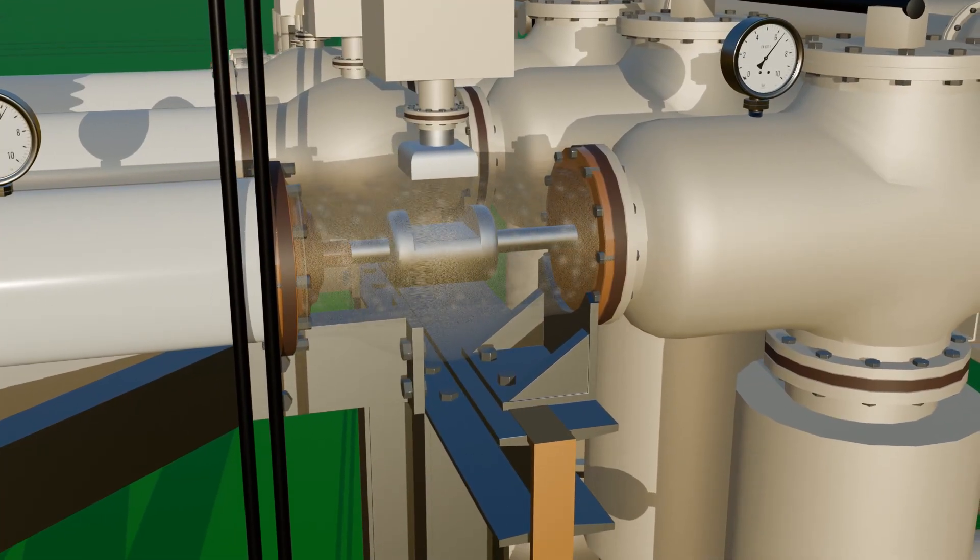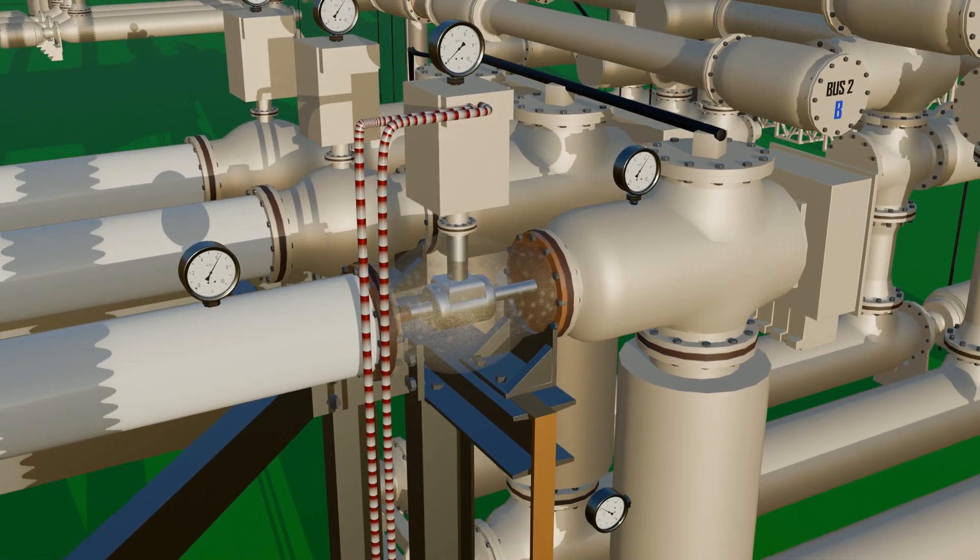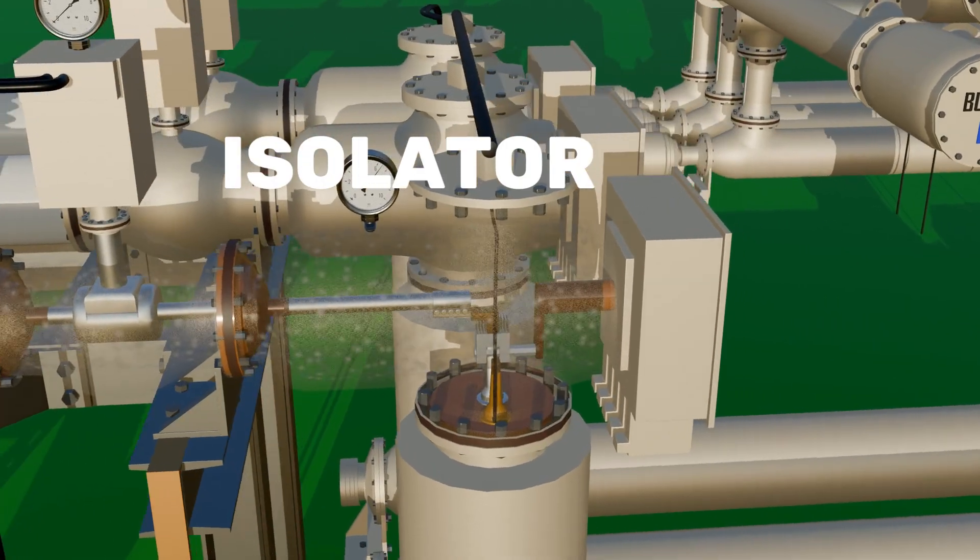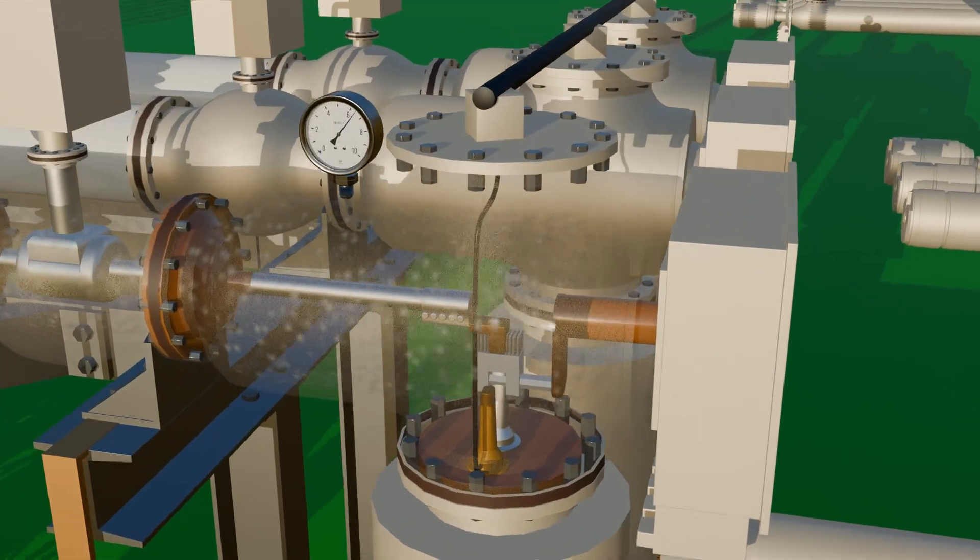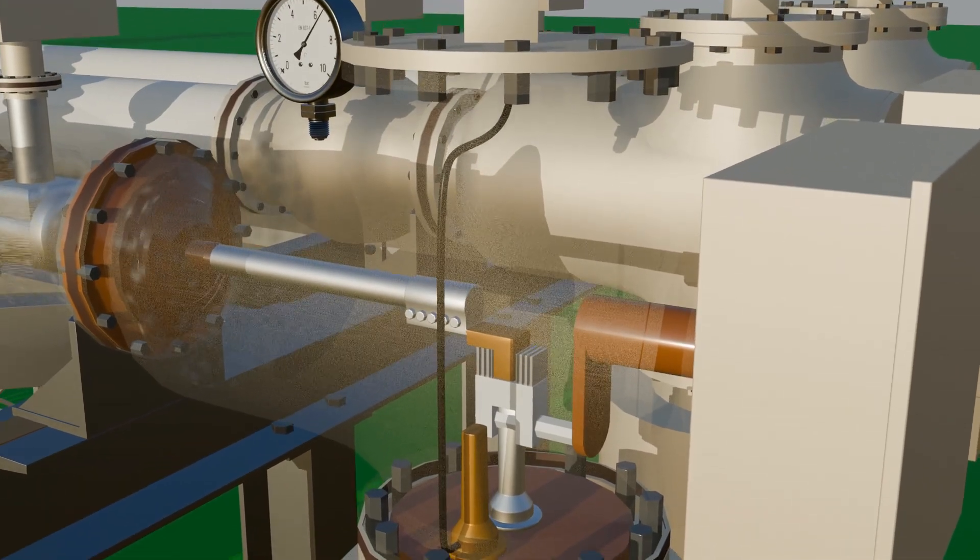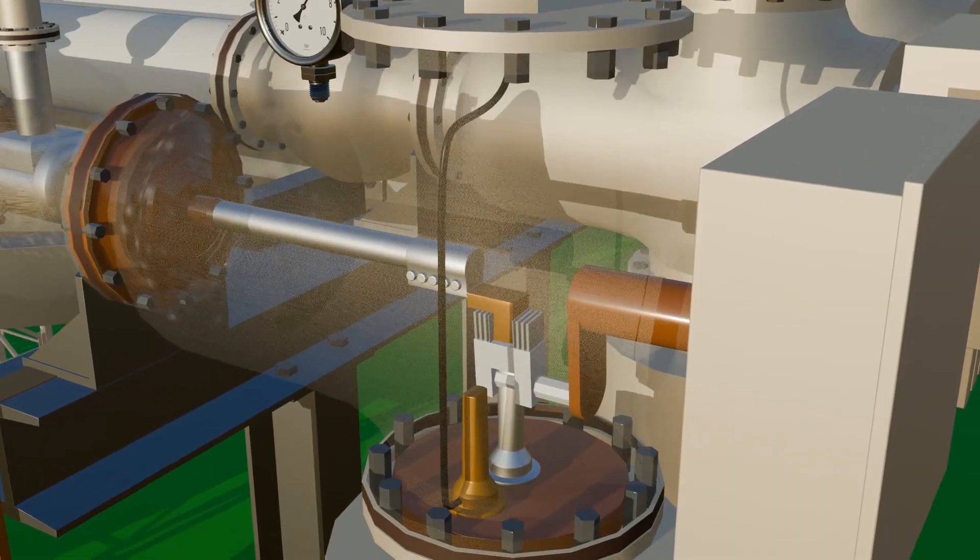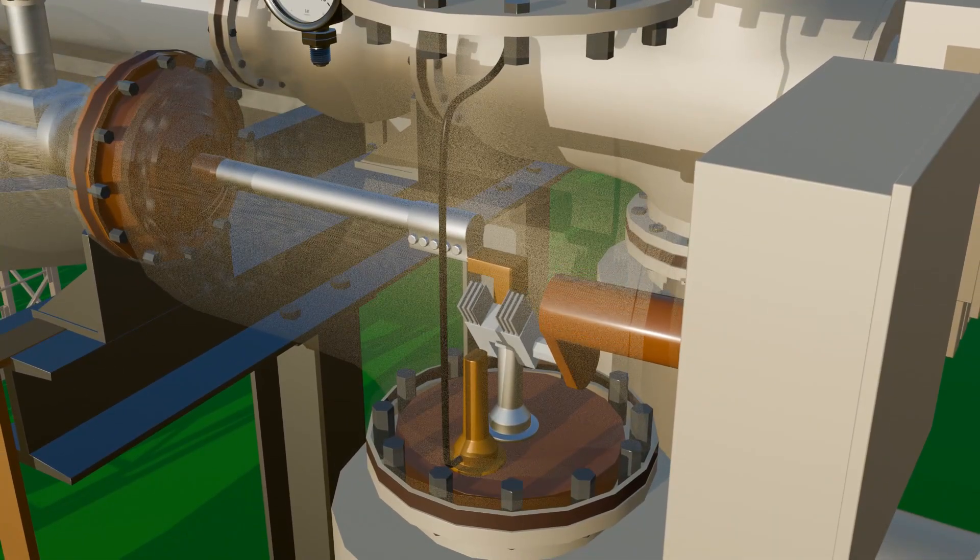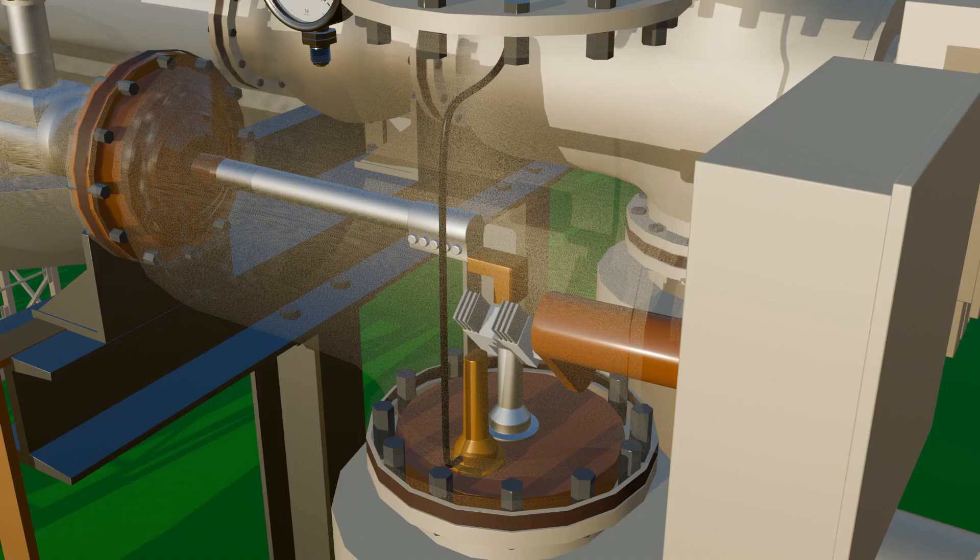Next comes the isolator block. An isolator functions like a normal switch. Its mechanism can be operated manually by rotating the moving contact to isolate the line. In GIS switchyards, isolators are typically motor operated. Once the line is disconnected, the moving contact is connected to earth again for safety.